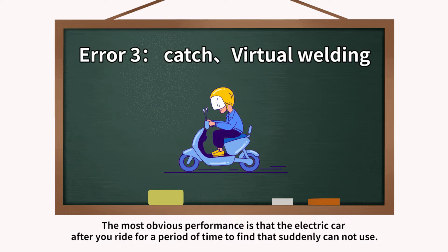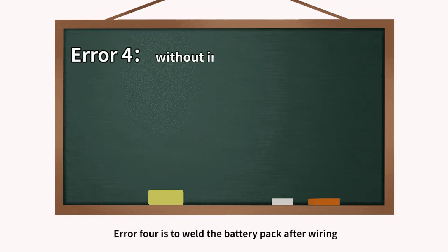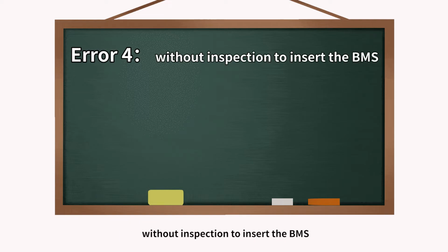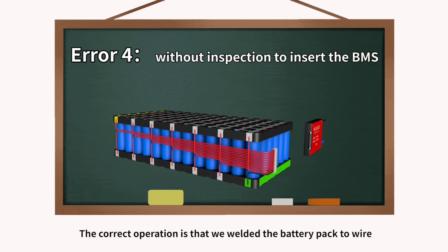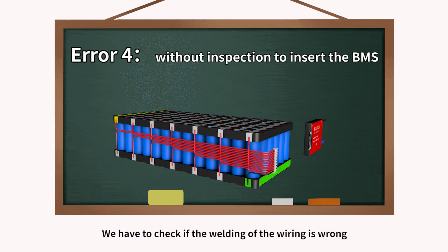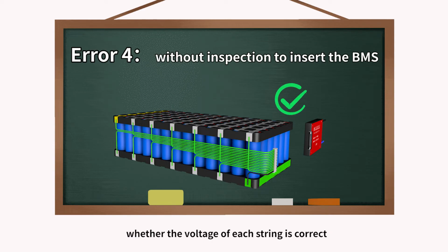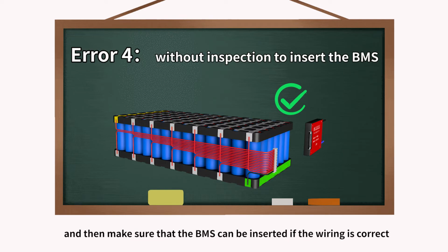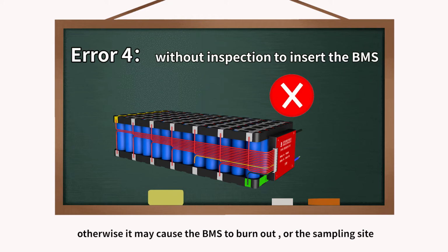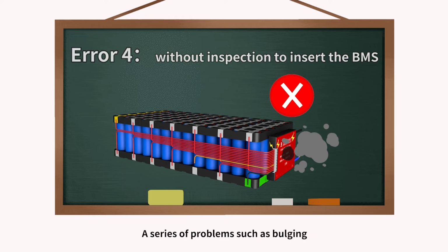Error four is welding the battery pack wiring and inserting the BMS without inspection. The correct operation is: after welding the battery pack wiring, we have to check whether the welding is wrong and whether the voltage of each string is correct, then confirm the BMS can be inserted only if the wiring is correct. Otherwise it may cause the BMS to burn out, or cause sampling site bulging and other problems.